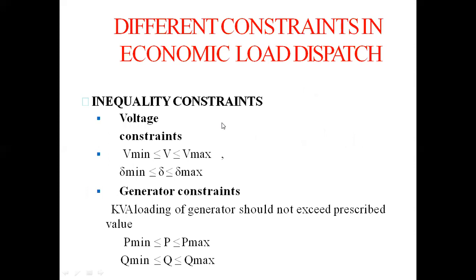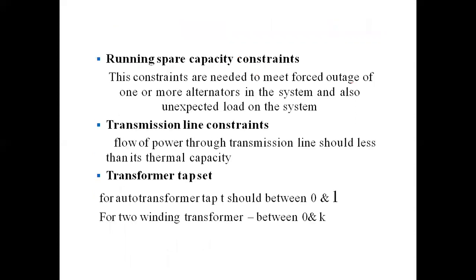Different constraints in economic load dispatch: first is the inequality constraints, that is the voltage constraints — the value of the voltage will lie between the minimum and the maximum value, and the angle delta will also lie between minimum and maximum value. There are also generator constraints — the KVA loading of the generator should not exceed the rated value; active and reactive power both will remain within maximum and minimum values.